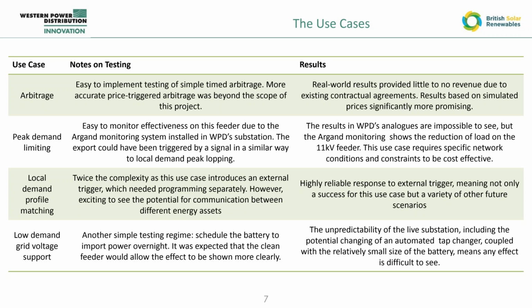Peak demand limiting. This is network support. So you try and reduce the max annual peak seen by the network and avoid reinforcement. This was expected to be useful in areas going forward which have slowly increasing demand, and then it would help equipment stay within their limits.